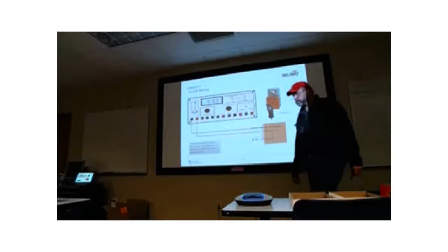So if you hook up just the red and the black wire, leave the white wire off, which way is the actuator rotating? It's slow. Should be clockwise. If it's counterclockwise, you have the switch in the wrong position. Yep. So it should be going clockwise. Okay. So everybody agrees it's going clockwise? Okay. Switch the switch to the 0 position and see what happens. No, not there, on the actuator. So now it's going counterclockwise, right?